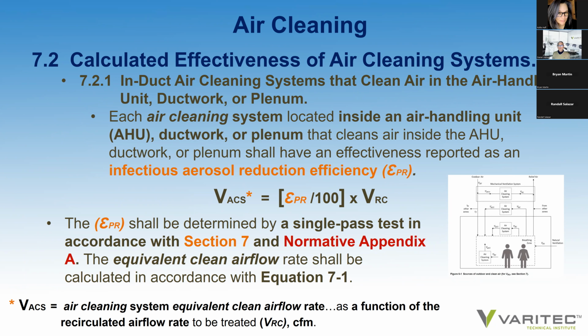And each air cleaning system located inside an air handling unit, ductwork or plenum shall be assigned an air cleaning system flow rate based on the aerosols divided by 100 times the amount of return air being served by that system. So the infectious aerosol reduction efficiency, epsilon PR, shall be determined by a single pass test in accordance with section 7. So now building designers have a standard to lean on with the application of air cleaning equipment. That's standard 241, section 7, or normative appendix A, which I'll look at quickly here shortly. And they will help assure a design team that the equivalent clean airflow is being achieved by that device, providing it passes the testing conformance.